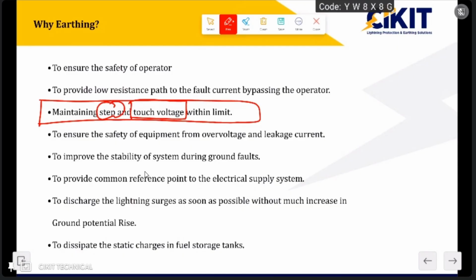Even if a person is walking in the substation area, if the ground potential is higher and there is a sufficient potential difference between the two feet of that person, he may get electrocuted. So when working with a substation, the most important parameter is the step and touch voltages. We need to ensure that the step and touch voltages are within the limits, to protect people from electrical hazards.